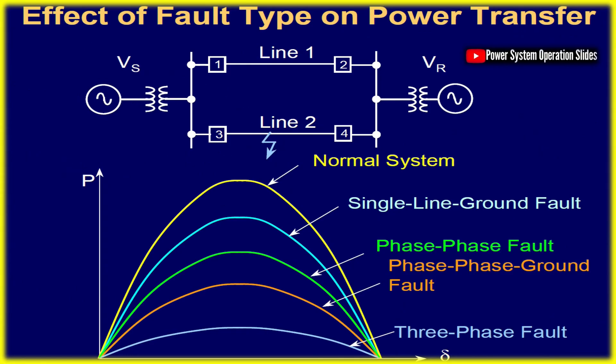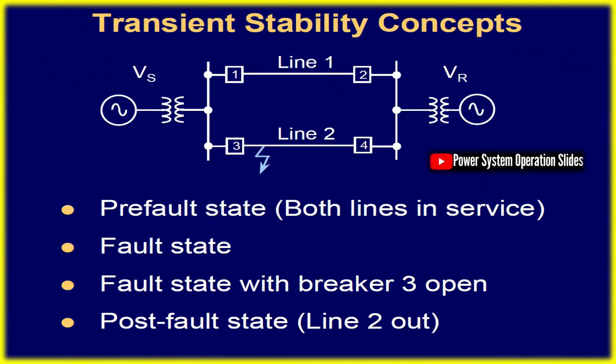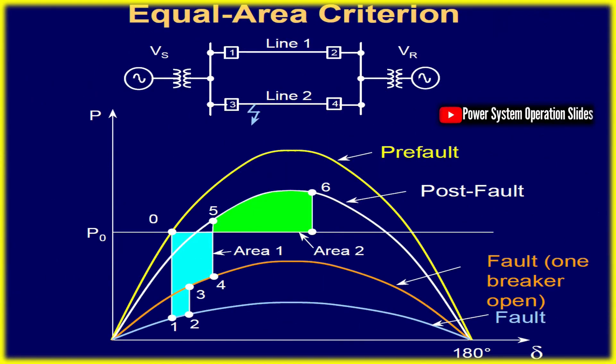OOS occurs when a generator loses synchronism with the system due to disturbances or automatic voltage regulator failures, leading to high peak currents, mechanical stress, and pulsating torques necessitating separation through OOS tripping relays.